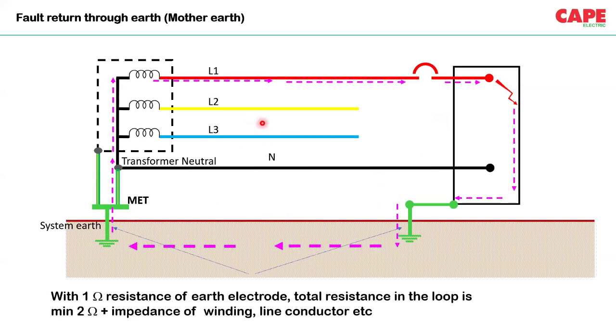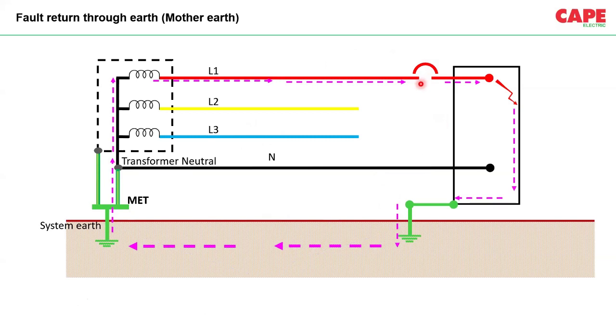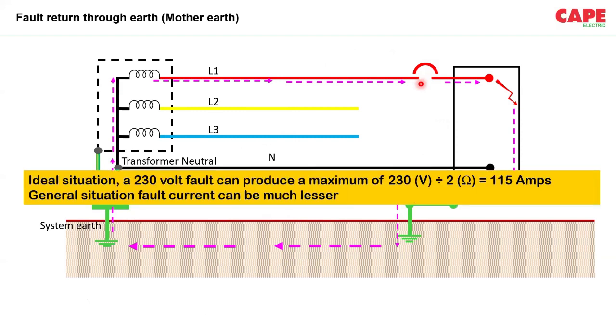So 2 ohm is additionally added in this particular loop. As a result, current will be much lower. Once the current is much lower, the protective device OCPD will not create an automatic disconnection, or that particular device is not efficient.